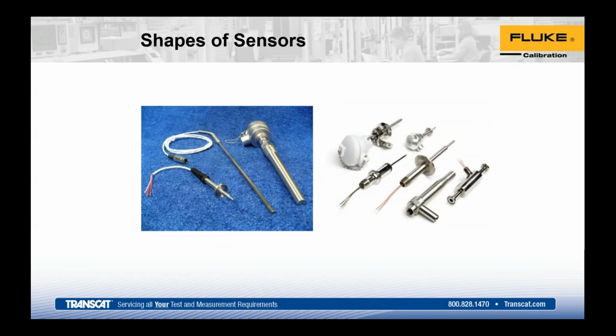The next biggest one I come up against is shapes of sensors. In the industry, a lot of folks just make the sensors, and then another manufacturer will take that sensor and embed it into their design. I've seen these come in very large diameters, very short, high temp, low temp. The hardest one I still come up against today is very short sensors that are capable of very high temperatures. Those become very difficult because it's hard to get a good overall heat source and reference set up where you only have, say, 2 or 3 inches of immersion.